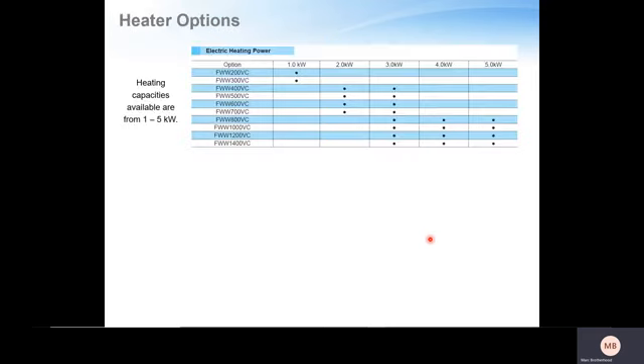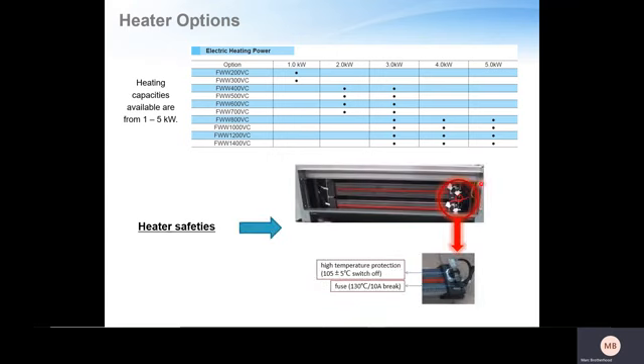The units also can come with heating elements. We go from 1 up to 5 kilowatts, 5 kilowatts generally on the 14 kilowatt units. Very importantly, choose the heater safety. We have 2 heater safeties. The first will be your bimetal switch, which will typically open when the heater runs away, if you want to call it that, and as it cycles on and off, it will pulse. With the bimetal switch at 105 degrees plus or minus, it will open and break, open and break.